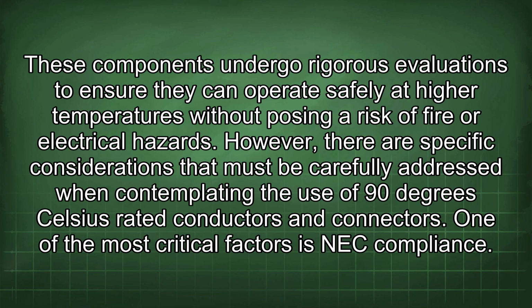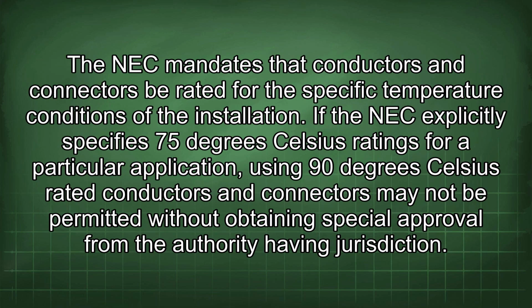One of the most critical factors is NEC compliance. The NEC mandates that conductors and connectors be rated for the specific temperature conditions of the installation. If the NEC explicitly specifies 75 degrees Celsius ratings for a particular application, using 90 degrees Celsius rated conductors and connectors may not be permitted without obtaining special approval from the authority having jurisdiction.